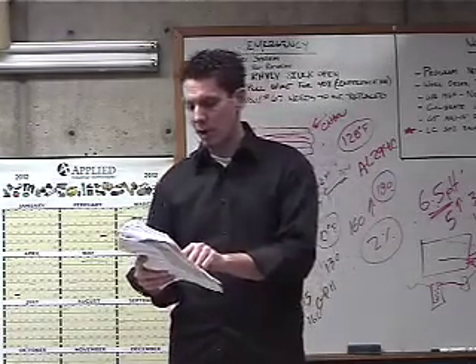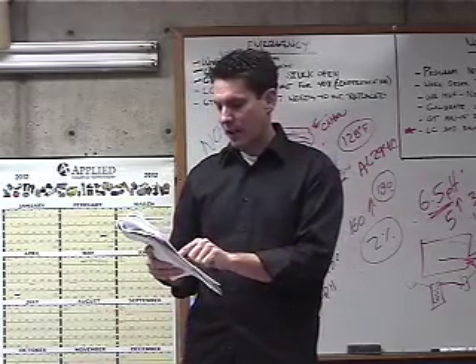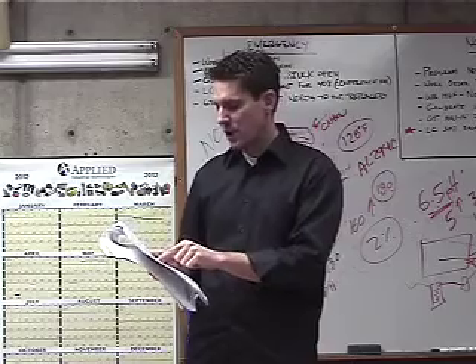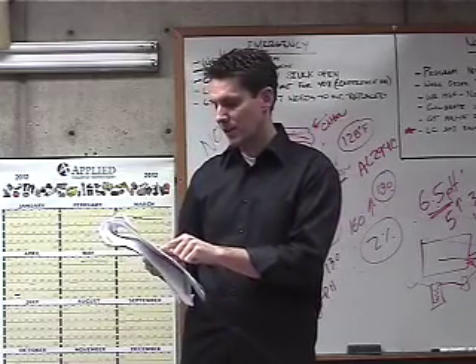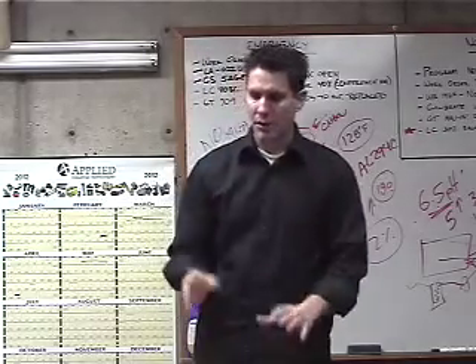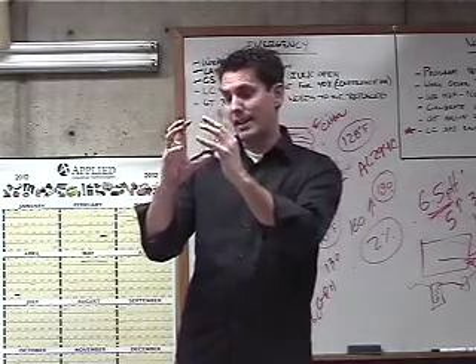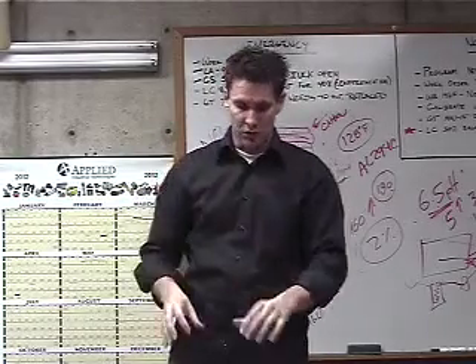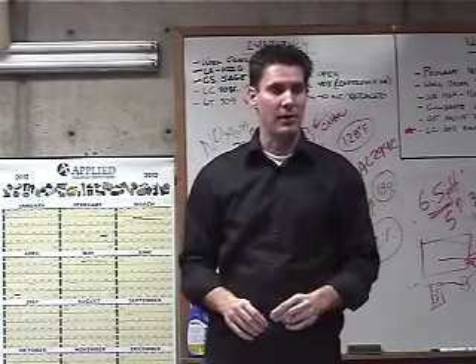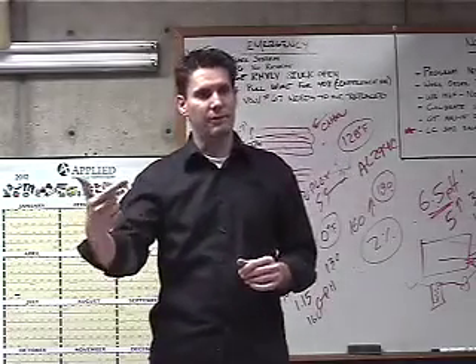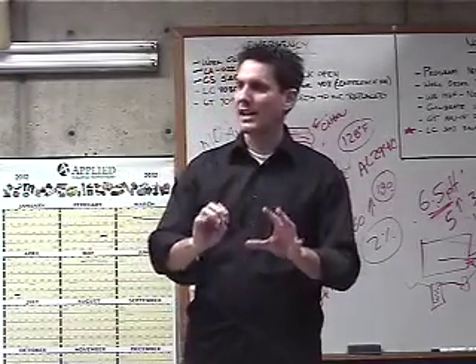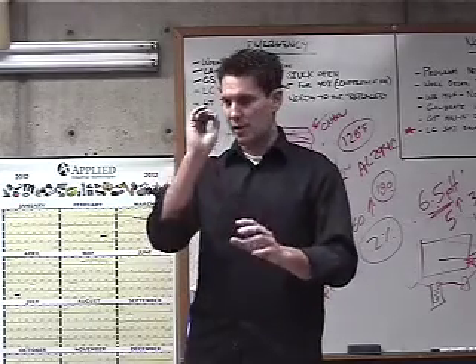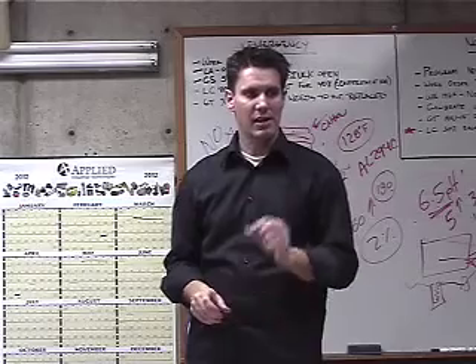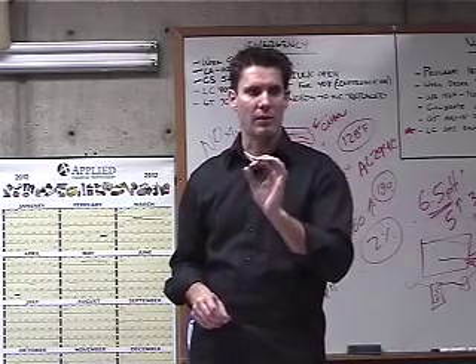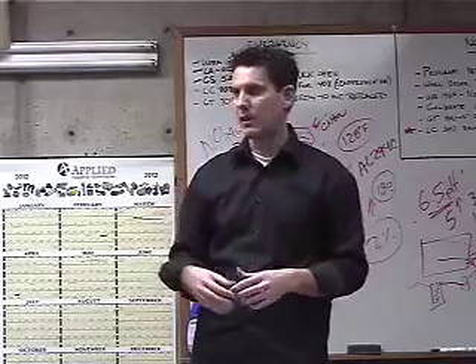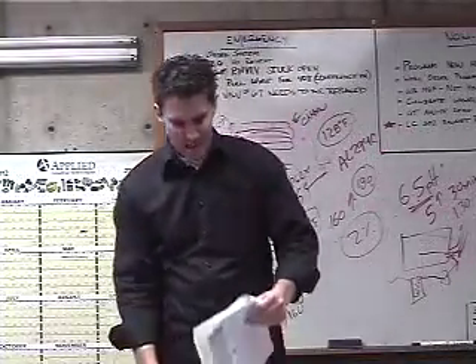In low fire, the burner should display a reddish orange glow. Correct air adjustment is essential for the efficient operation of this boiler. If an adjustment to the combustion is necessary, that's the flue gas composition. So don't look down there, see the flame and it's a bad color, and say okay, I'm going to get in and change my positions on my valves. Don't do that. You've got to plug in your flue gas analyzer first, find out where your CO2 is, and then dial that CO2 level in to where it needs to be. It's not just a visual test. The percentages are very small and very minute, and they can change very quickly depending on what fire rate you're operating at.